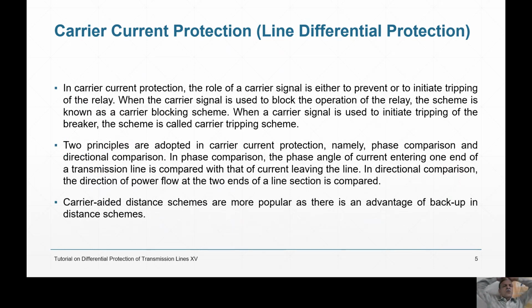Carrier current protection is used in two ways. Either the carrier signal will trip the relay, then it is a tripping scheme, or it will block the operation of the relay, then it is a blocking scheme. Right. So there are two schemes, blocking scheme and tripping scheme. When carrier is received and the tripping is blocked, that is a blocking scheme. And if carrier is received and tripping is allowed, that is a tripping scheme. So we will study first the phase comparison or directional comparison scheme.